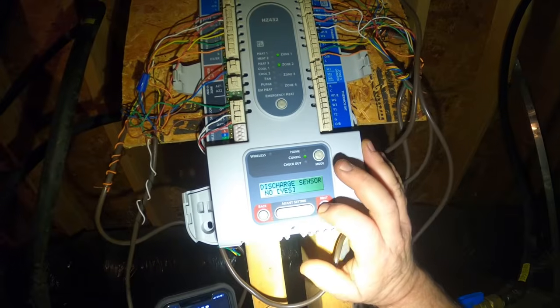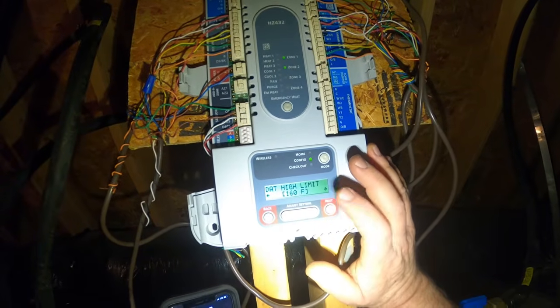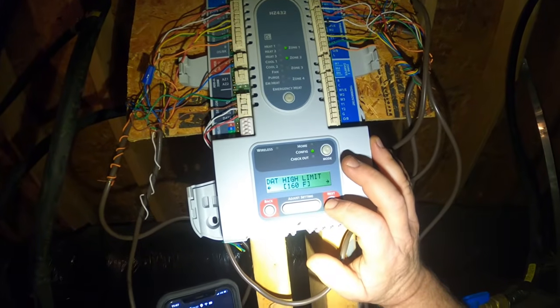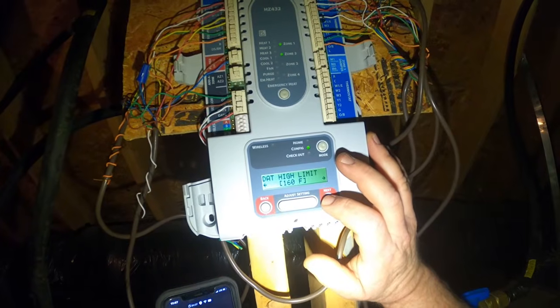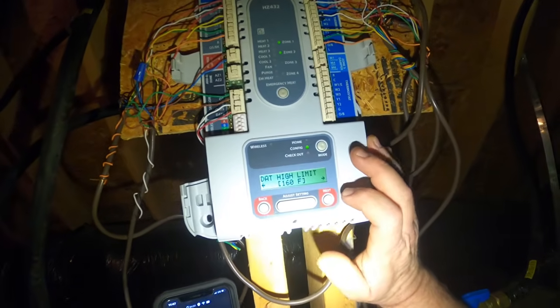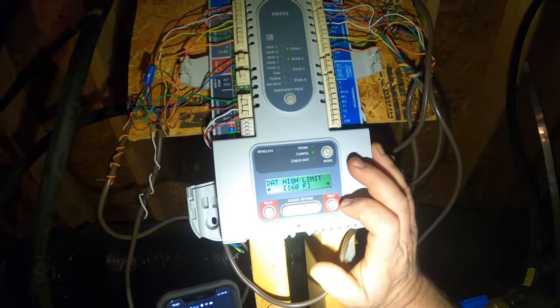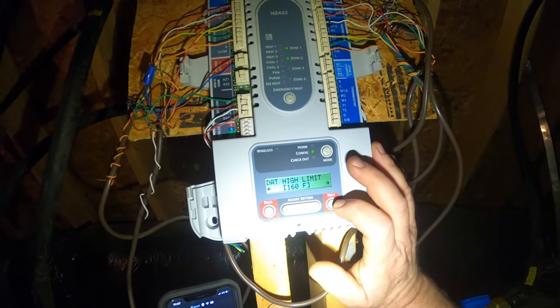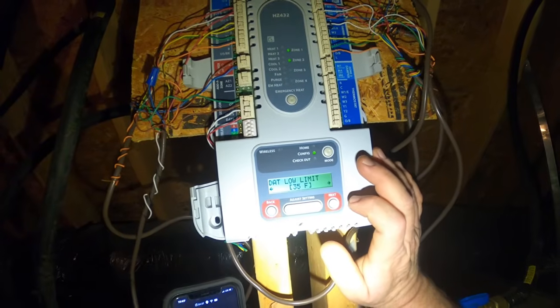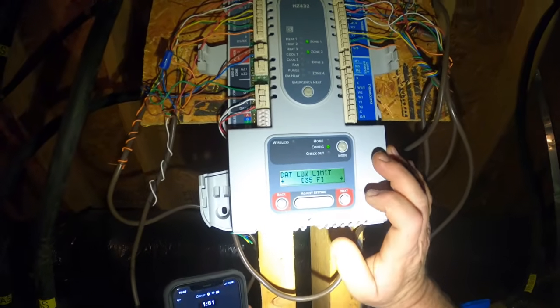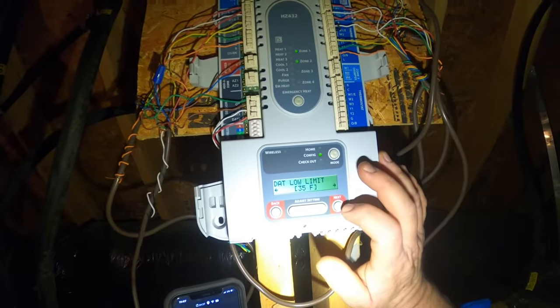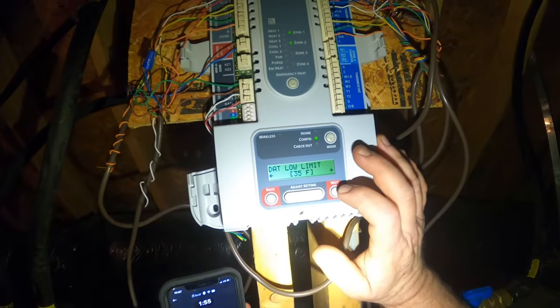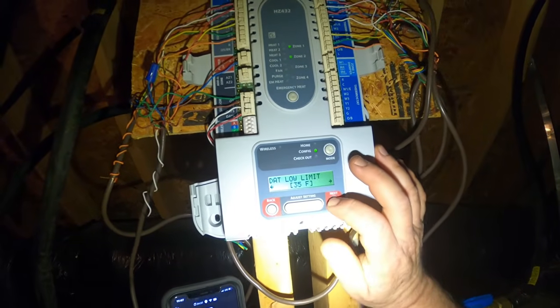Discharge sensor installed, yes. DAT, we're going to set our high limit at 160, so if it gets above 160 in the plenum, the blower quits or damper motor sticks, whatever happens. If it gets above 160 in heat mode, it'll shut the equipment off. And if it gets below 35 in cooling mode, if one of those things happens, to prevent a freeze up, it'll cycle it off. And once the temperature stabilizes back, it'll turn everything back on.